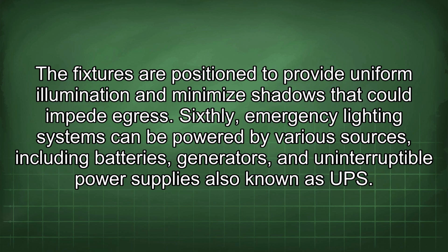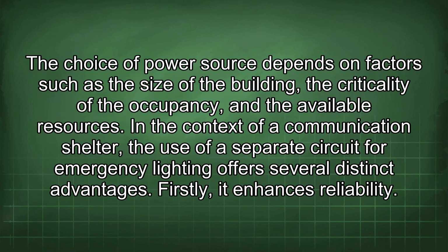Sixthly, emergency lighting systems can be powered by various sources, including batteries, generators, and uninterruptible power supplies, also known as UPS. The choice of power source depends on factors such as the size of the building, the criticality of the occupancy, and the available resources. In the context of a communication shelter, the use of a separate circuit for emergency lighting offers several distinct advantages.